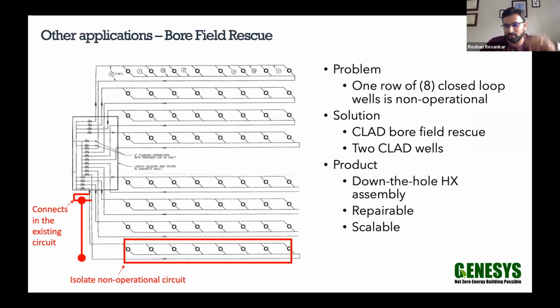We came across a pretty critical project which had 8 boreholes on each circuit and 8 circuits, so a total of 64 boreholes, and they noticed that there were leaks in the circuit. They couldn't figure out where it was. They had to isolate the entire circuit. They suspect there is another leak in another circuit, and they might have to isolate that as well.